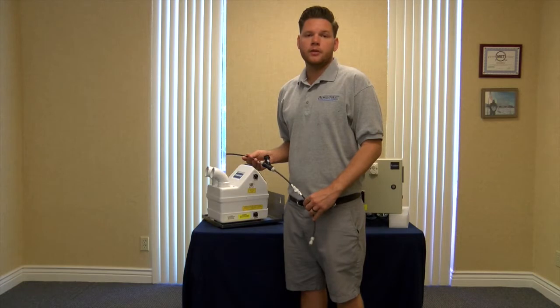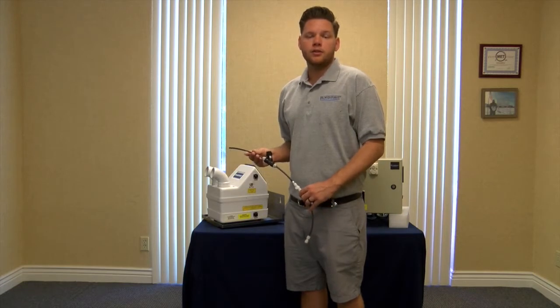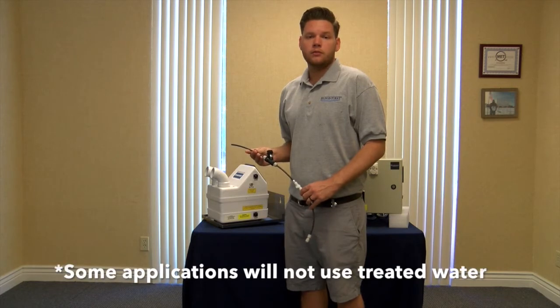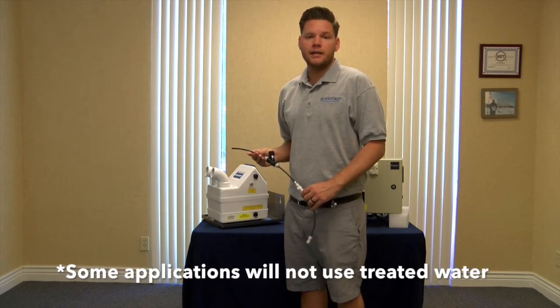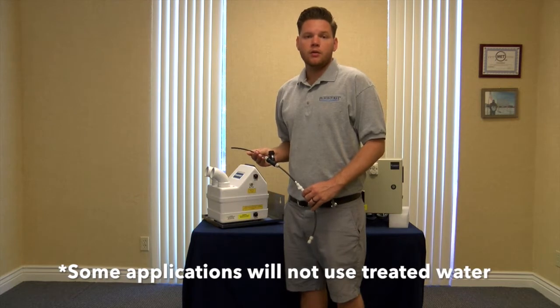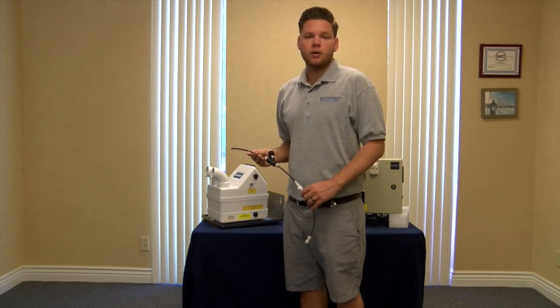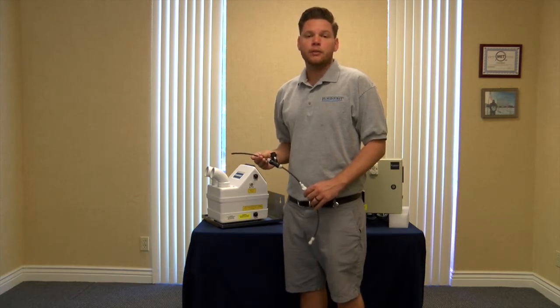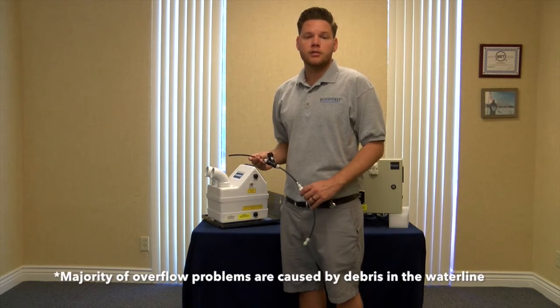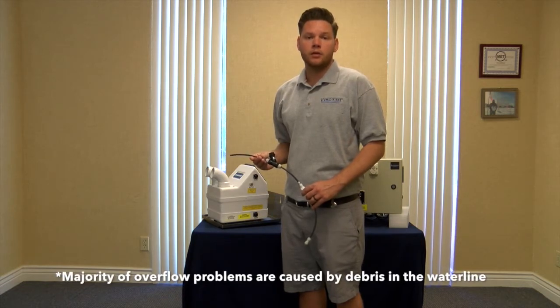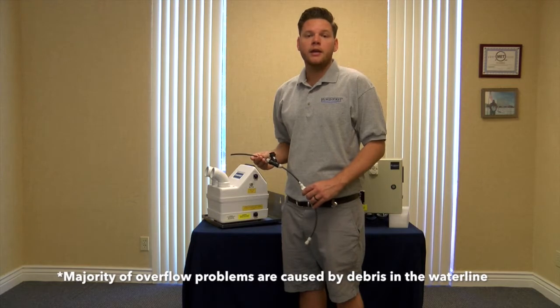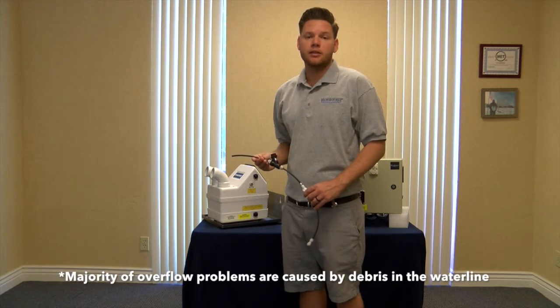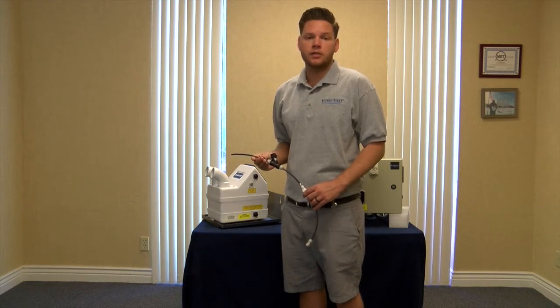Before plumbing your humidifier, you want to make sure you are using treated water. RO, reverse osmosis, or DI, deionized water. Once you have ensured you are using treated water, you want to make sure you bleed all water lines before plumbing the unit. Bleeding all the water lines ensures there is no debris in your water lines that could get caught in the solenoid inside of the humidifier, causing an overflow situation.